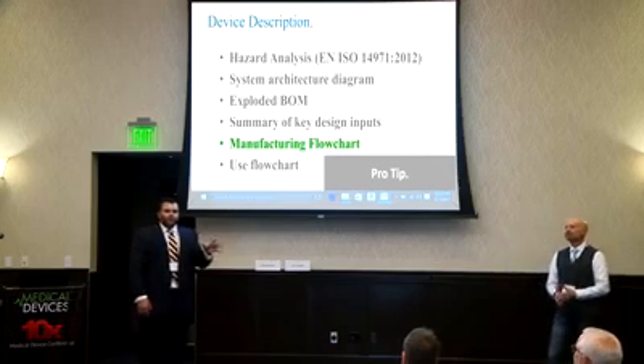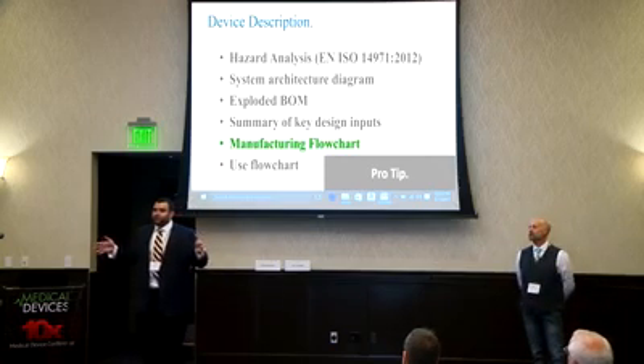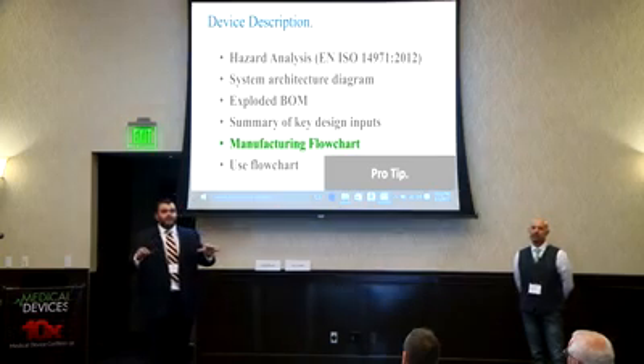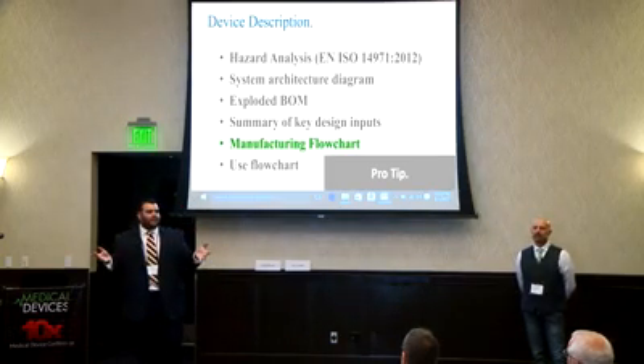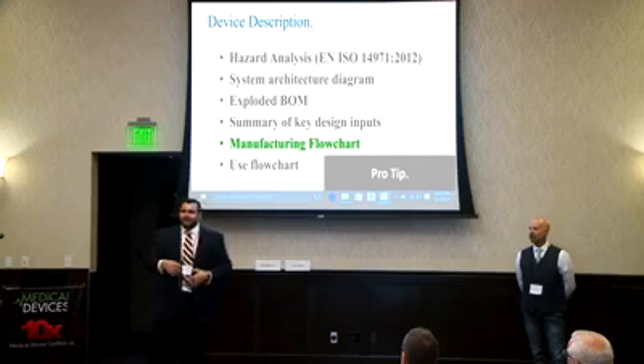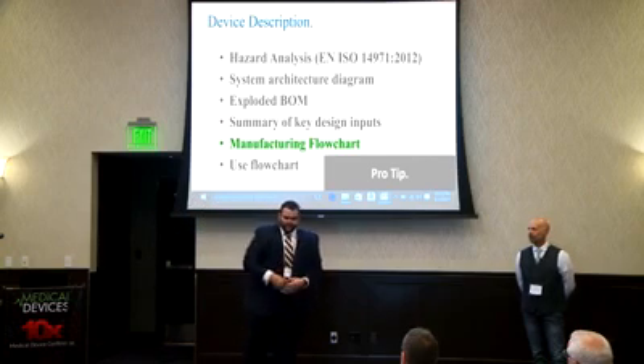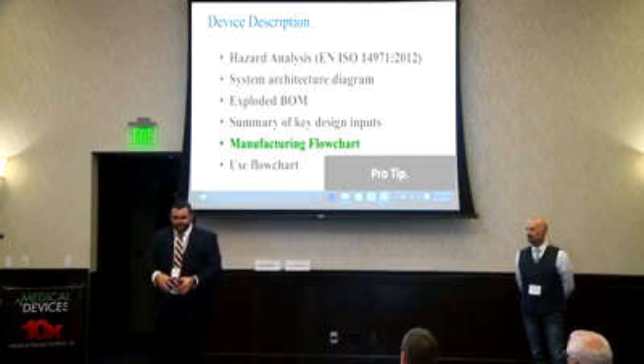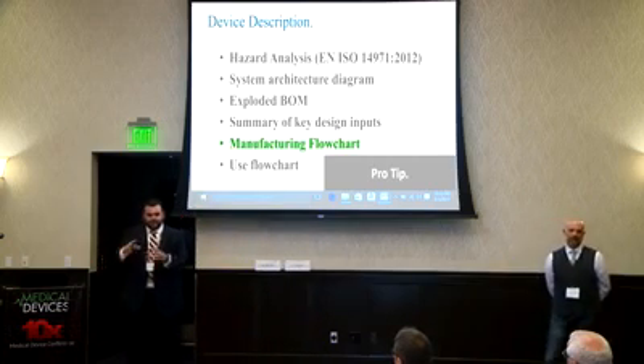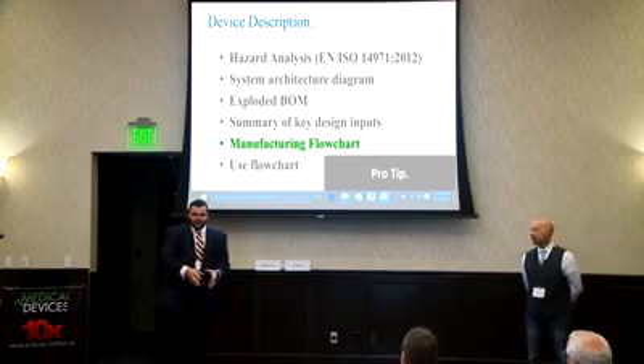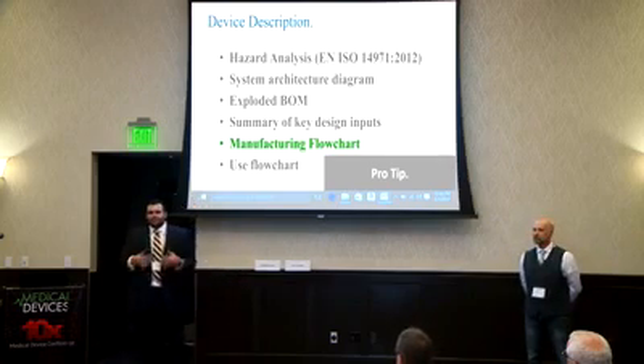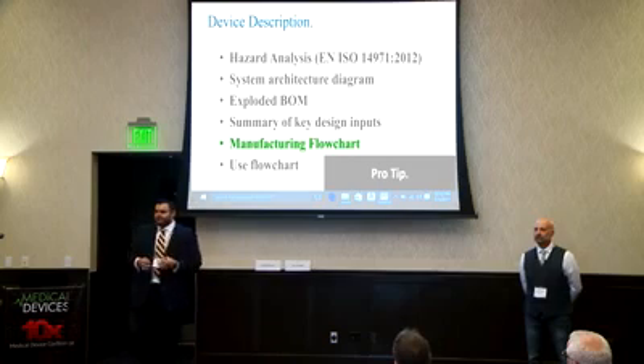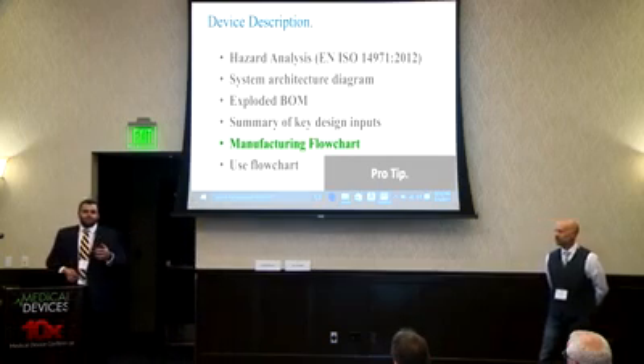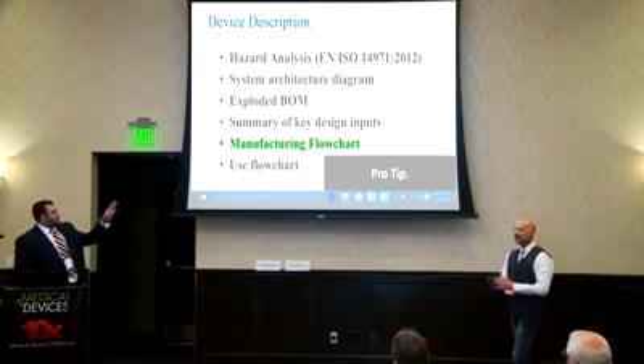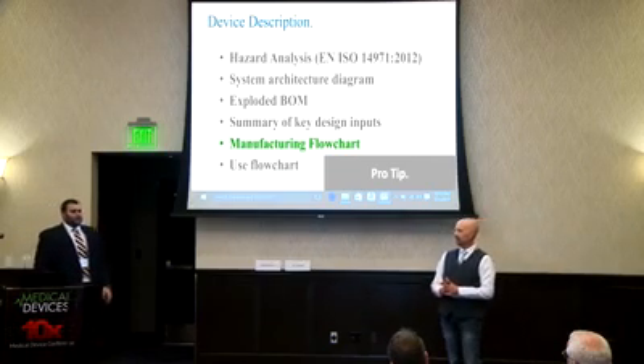That's one of the biggest reasons I always want to have a manufacturing flowchart. Again, to the extent that it is known, right? You're not going to have all the details. You don't have to name names, but having at least a rough manufacturing flowchart. Hey, we're going to do molding here, then final assembly at a different facility, and sterilization at another facility, and it's going to go back to the final finished good manufacturer. That's sufficient. But just letting them know what that is, because you'd be surprised how many of these little things become huge issues at submission time. So these are some key tips for the device description section.